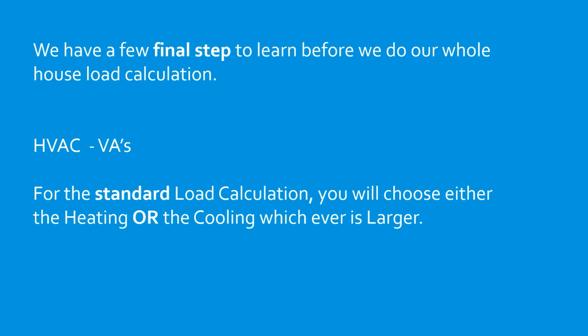And the thing that we have to watch out for is that we're only going to use one or the other, unless for some reason your question states that both are going to be running at the same time, or maybe even your real world scenario, both of them are going to run at the same time. But pretty much across the board, I've never seen anything but either or. So with the standard method, you're either going to choose the larger of the two. It's either going to be the heating or the cooling.